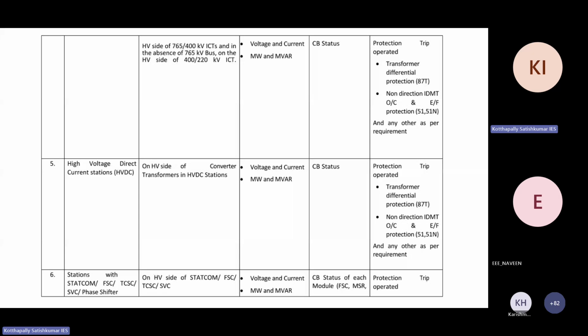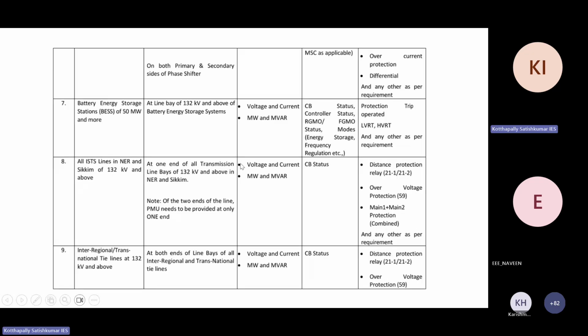As I told, these are the HVDC substation or regenerating stations, and also STATCOMs, FSC, TCSC, wherever these static controllers are there, we mandated them to place PMUs, because these are electronic devices. We want the data from them, their behavior during fault, since these are critical components of the system. We want to monitor and see the data for analysis purposes. And upcoming battery energy storage systems of 50 megawatt and above.